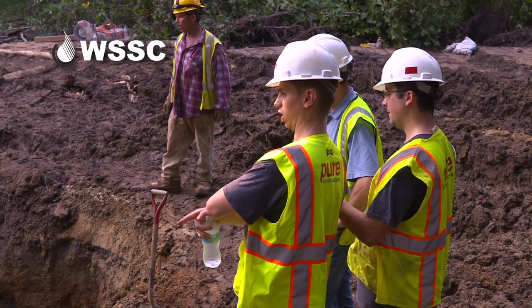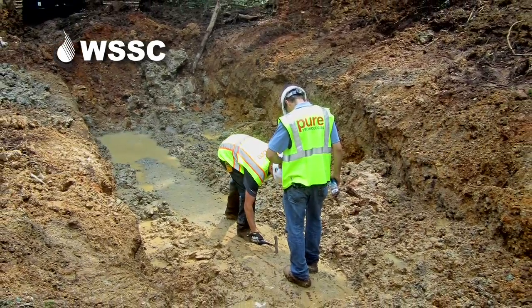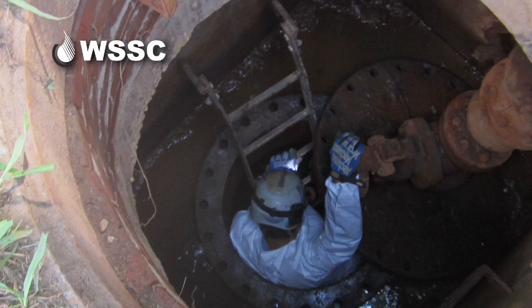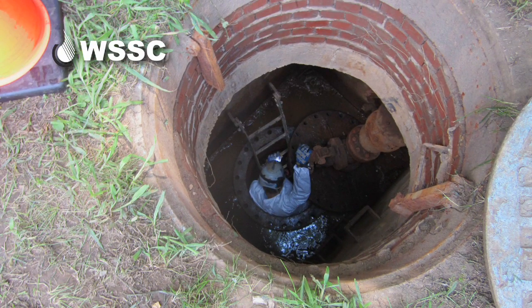The AFO consultant was on standby, ready to confirm the location to dig. A hammer tap on the top of the pipe is recorded by the AFO, and those sound waves confirm the location. The consultant must then go inside the main and manually remove the AFO cable before the bad section of pipe can be cut out.